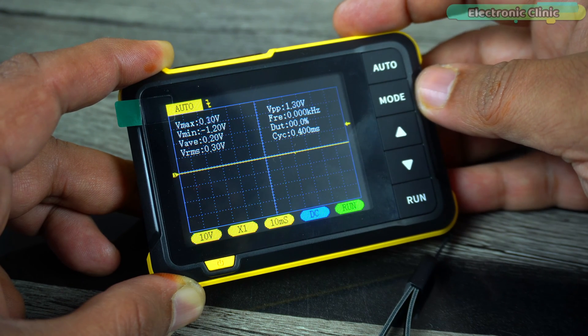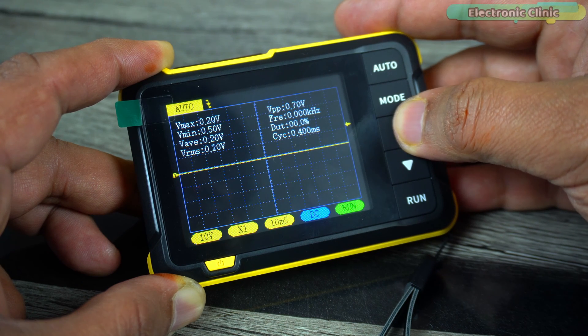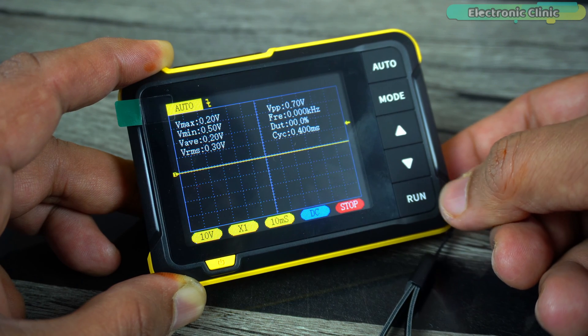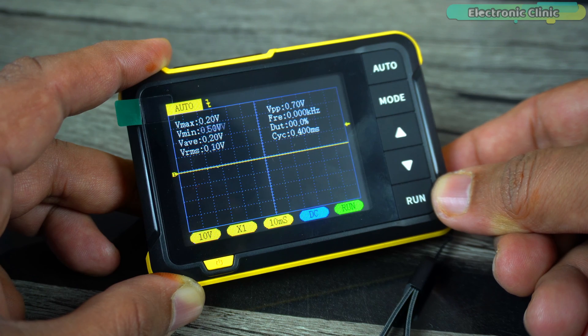Next is the AC or DC coupling indicator icon — AC means AC coupling and DC means DC coupling. You can control the run parameter using the run button: run means running and stop means pause. That covers pretty much everything, and now it's time to connect the probe.